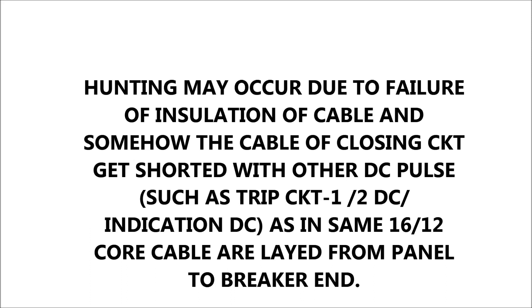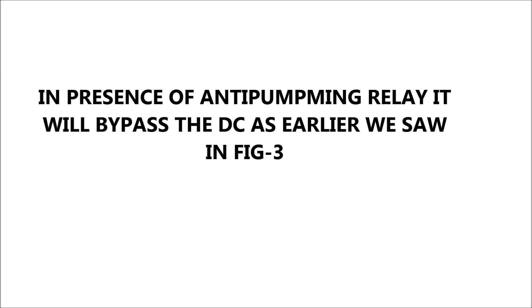In the same control cable — that is, a 12 or 16 core cable — different cables are laid from the panel end to the breaker end, carrying DC pulses from the control switch to the closing coil of the breaker: DC trip circuit 1 positive, trip circuit 2 positive, indication DC, and so on. Failure of insulation of a cable may lead to a situation where the closing circuit gets a continuous DC pulse from another cable, thereby causing hunting in the absence of an anti-pumping relay. But in the presence of an anti-pumping relay, it will bypass the closing pulse to the closing coil, as shown earlier in the circuit diagram.